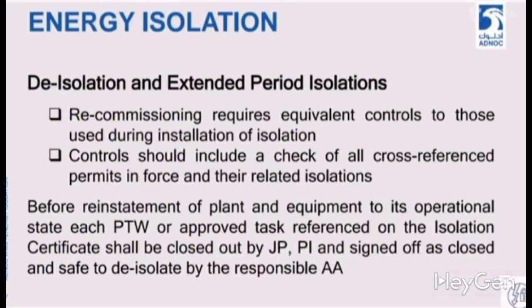What happens is that when we need to shut down an area, we isolate the battery limit. After isolating the battery limit, we start work by isolating multiple pieces of equipment inside. Beyond the battery limit, our unit is divided into more than 1, 2, or even 3 or 4 zones. Each crew may be assigned a particular piece of equipment. Some crews will perform valve replacement. Some will work on piping, and others will work on exchangers. We need to ensure that when we de-isolate the battery limit, all linked equipment ahead have their permits closed, and all individual isolation certificates are completed.